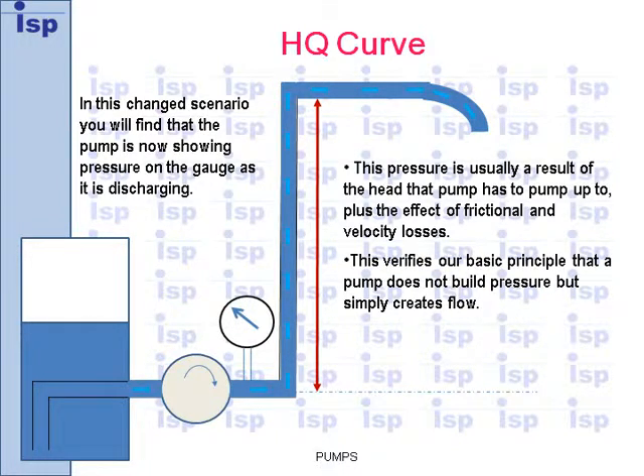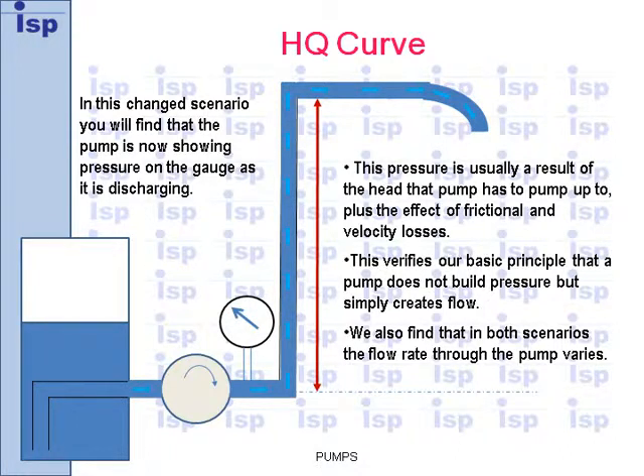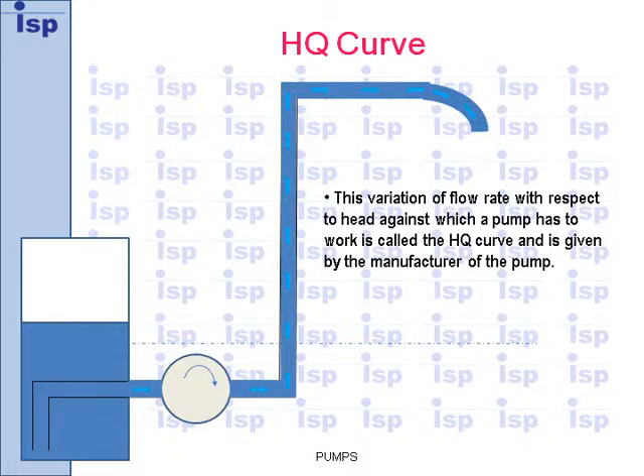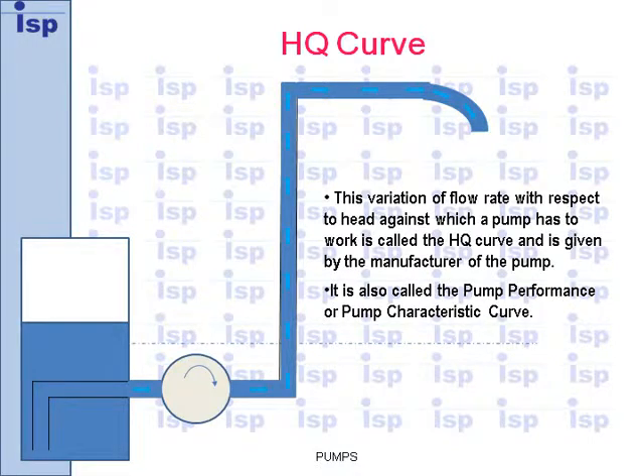This verifies our basic principle that a pump does not build pressure but simply creates flow. We also find that in both scenarios, the flow rate through the pump varies. This variation of flow rate with respect to head against which a pump has to work is called the HQ curve, given by the manufacturer. It is also called the pump performance or pump characteristic curve.